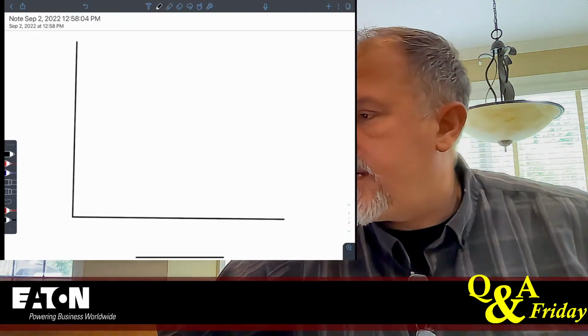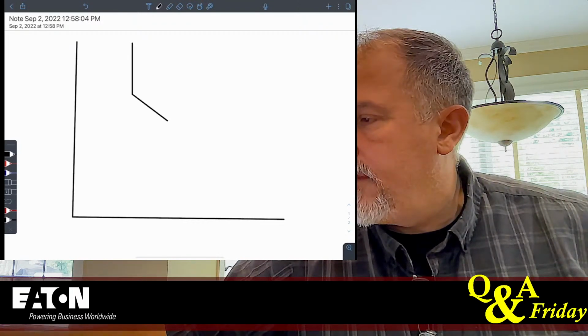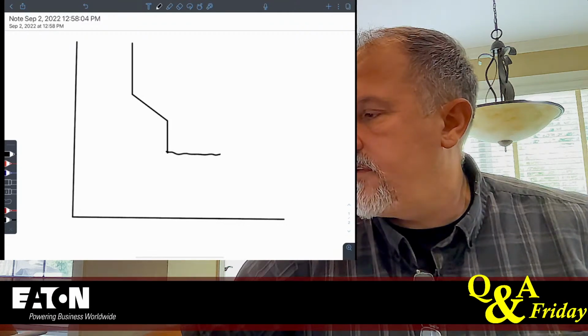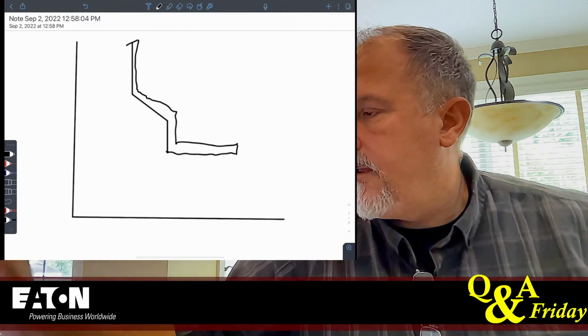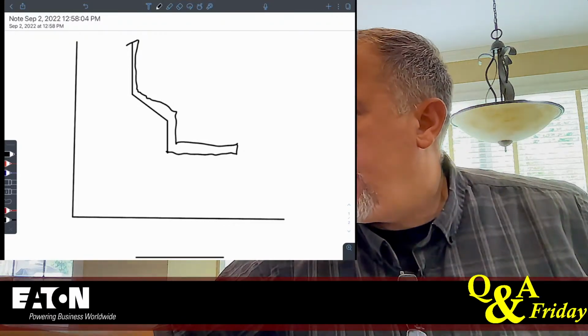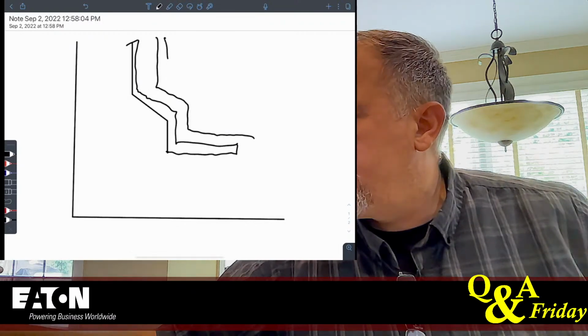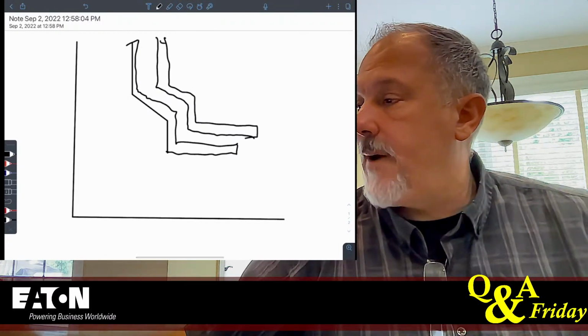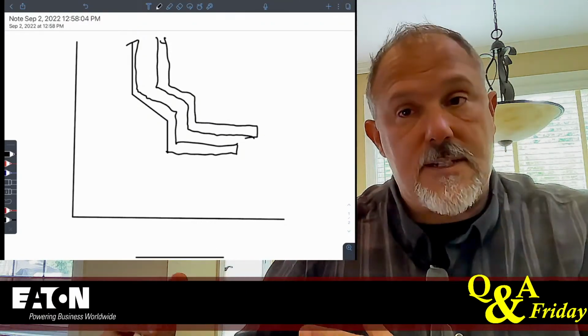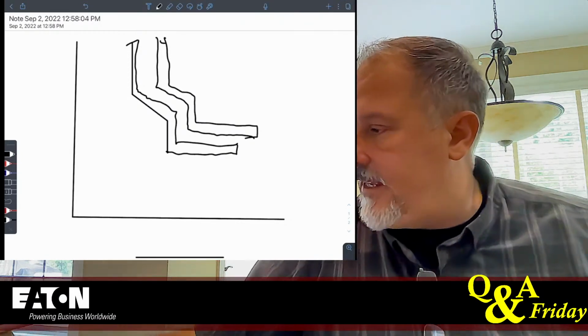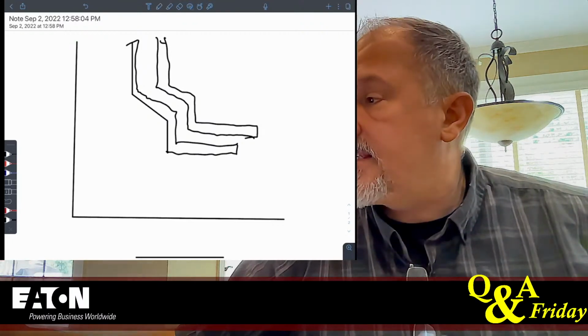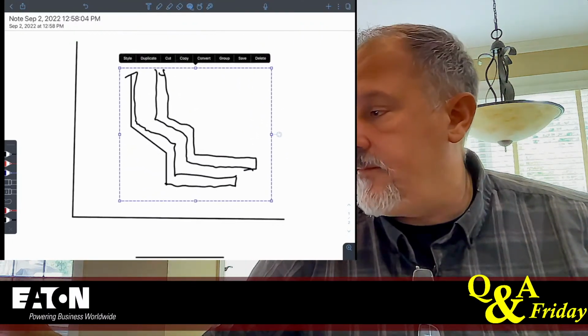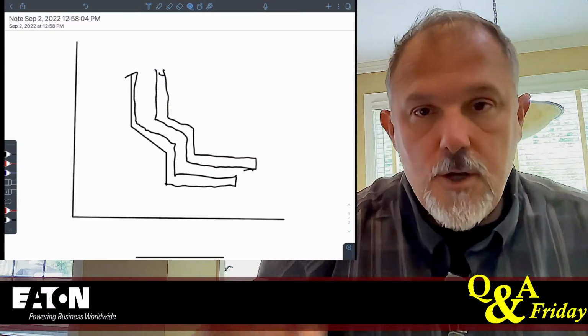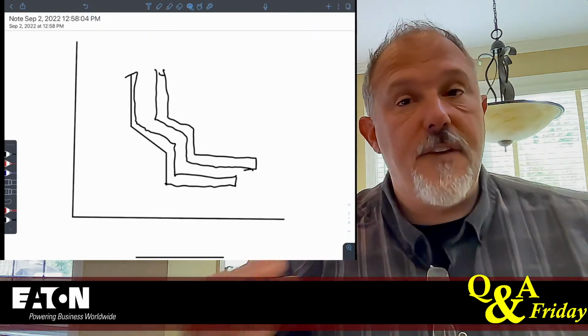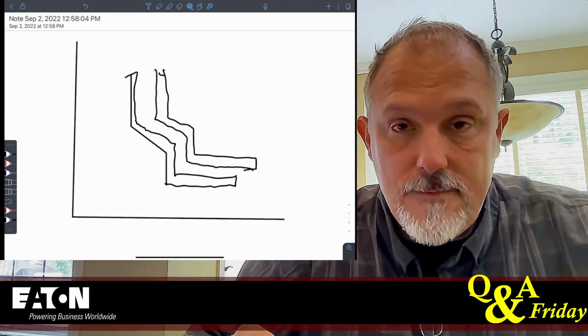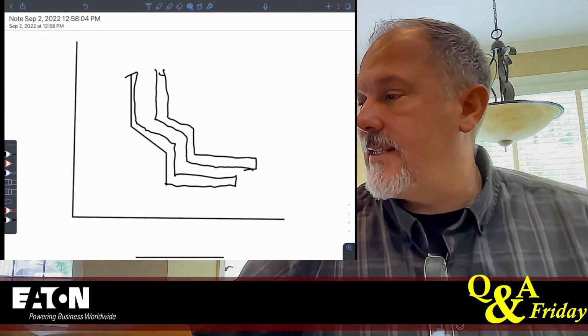All right, so here's, I'm just going to do this. So there's one breaker, and here is another breaker. If these are my power circuit breakers, right? So these are, say, power circuit breakers. I don't have an instantaneous, good to go, obviously. And now what I'm trying to say is sometimes the software will cut these curves off at the available fault current. And sometimes they don't. All right. And the reason I say that, let's say that you did this.